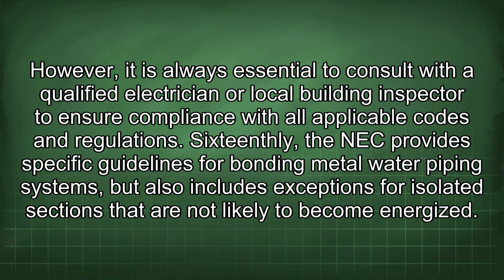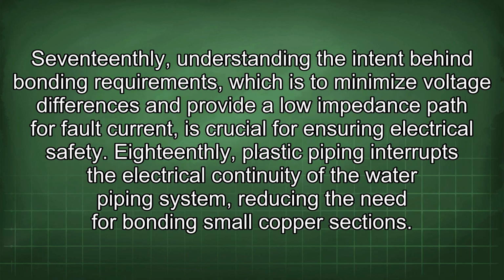16th, the NEC provides specific guidelines for bonding metal water piping systems, but also includes exceptions for isolated sections that are not likely to become energized. 17th, understanding the intent behind bonding requirements, which is to minimize voltage differences and provide a low impedance path for fault current, is crucial for ensuring electrical safety.